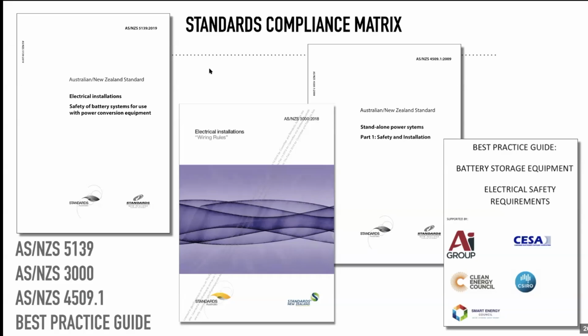AS/NZS 3000 always covers installation of wiring systems, including DC, including off-grid and on-grid systems. 4509 Part 1 is the standalone system standard for installation, and so it covers the requirements for installing systems standalone. I should point out that standalone doesn't mean you live in whoop whoop. It doesn't mean that you don't have the grid. It actually means that you're capable of running whenever you wish, independently of the grid.